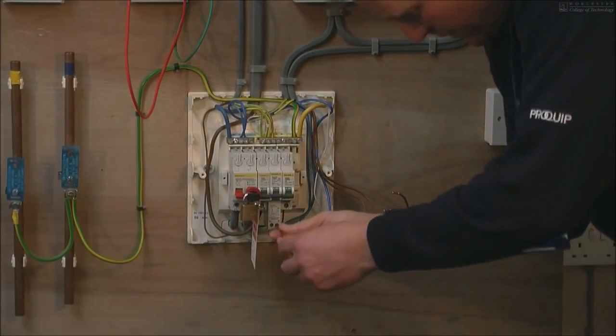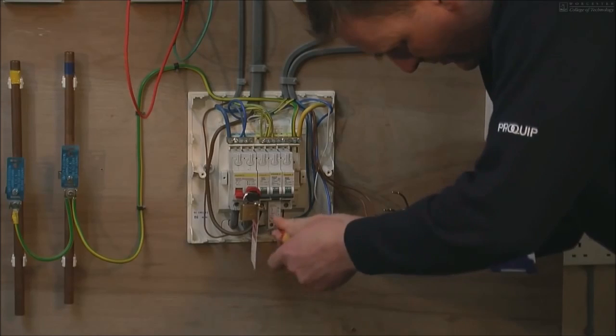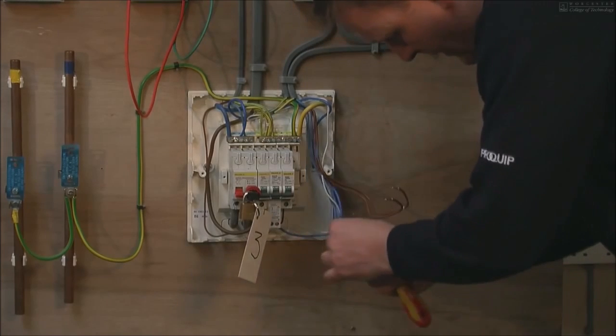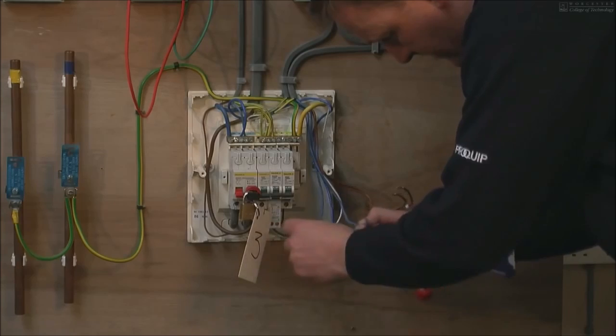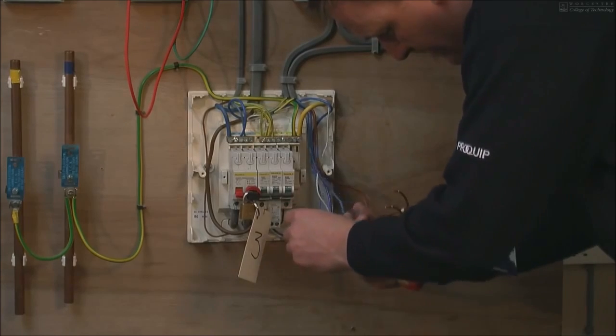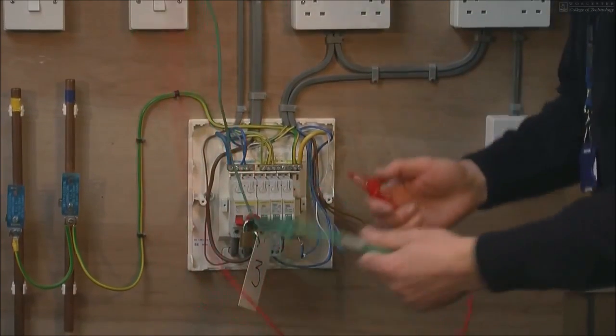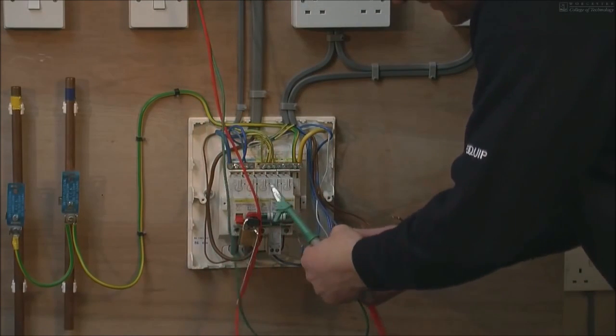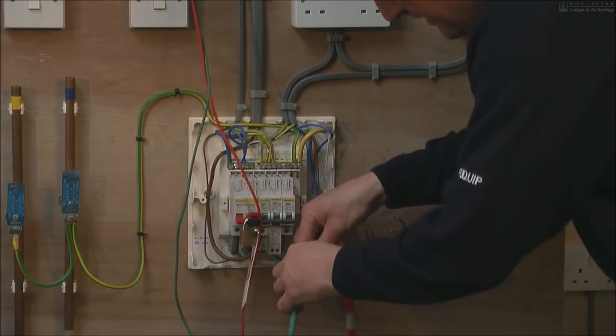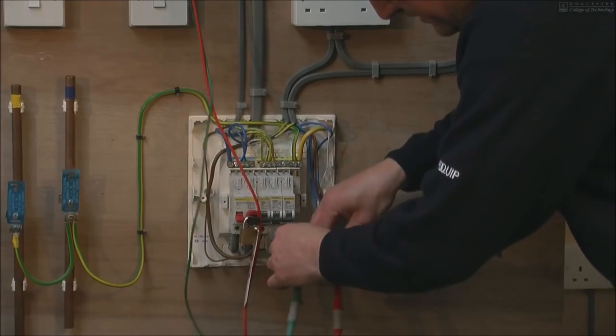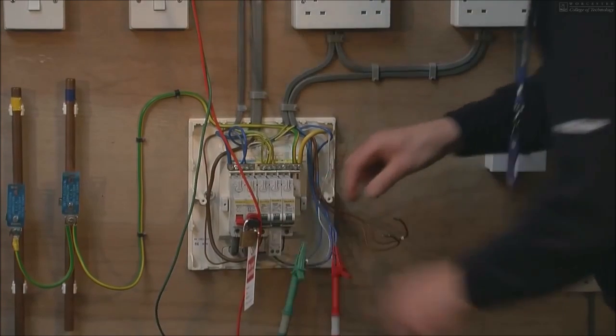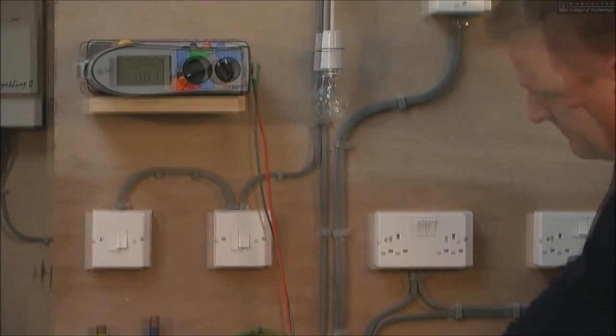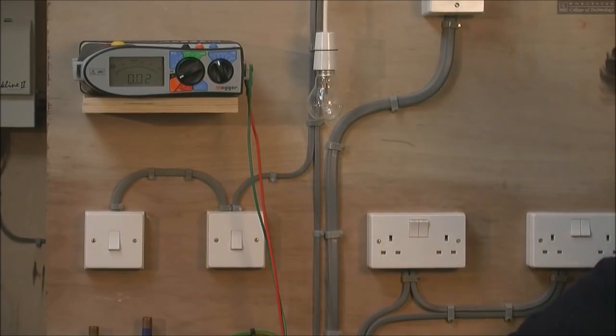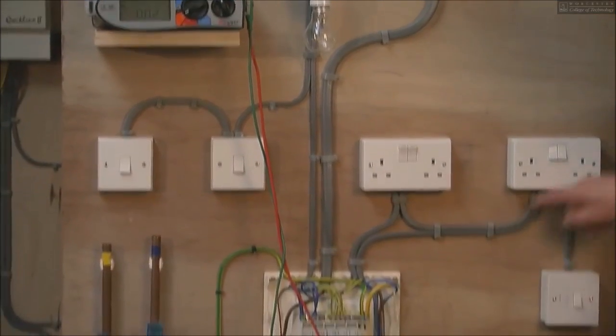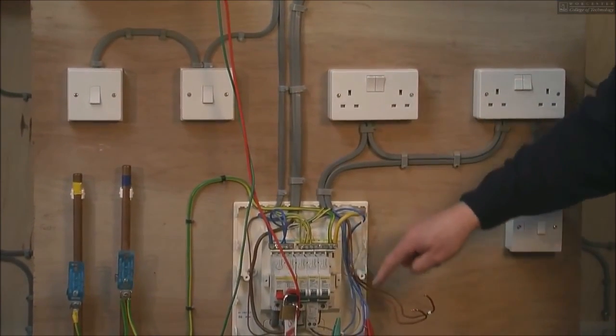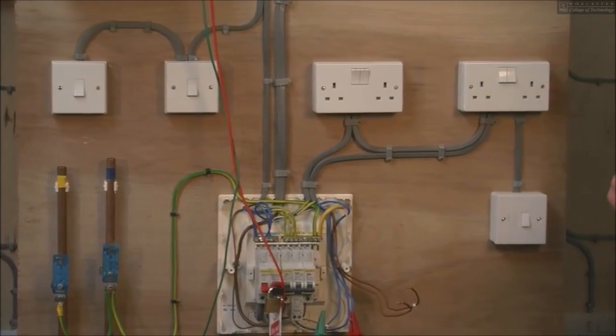We're now going to remove the neutral conductors and again separate them. We then take the test leads and we do exactly the same as we did with the line conductors. Make sure we give the crocodile clips a pinch. And this is ensuring that now the neutral conductor also is continuous through the circuit. And this is known as the little rn.